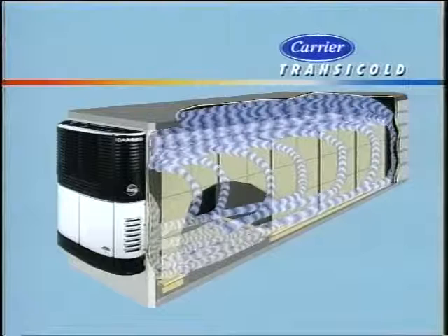The Ultima 53 with the advanced microprocessor system is designed to start itself automatically under normal conditions, although in cold ambients it may be necessary to start the unit manually, since a longer glow time may be required. The manual glow crank switch has been moved to the rear of the electrical box on the Ultima and on the side of the control box accessible through the front row side door on the Ultra, Ultra XL, and Extra. The switch is now easily reached from beneath the unit.